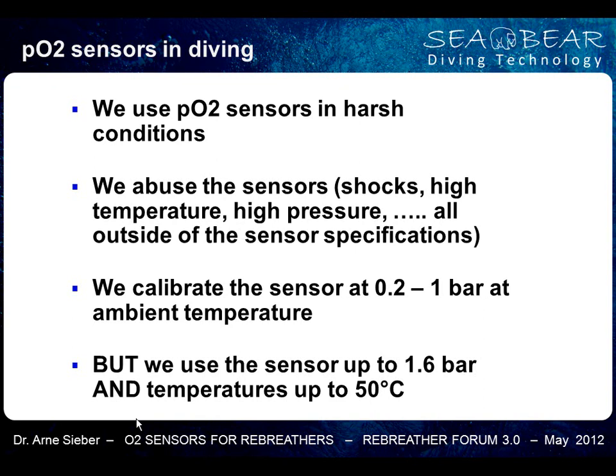The next thing is, we calibrate the sensor at 0.2 or maybe 1 bar PO2, and we're doing this at ambient pressure. But then when we are diving, we use the sensor up to 1.6 bar and temperatures up to 50 degrees, if it's at the exit of the scrubber. So this is not the same as what I have learned in the medical industry about how you should treat sensors. And this is when I said, this is not how it should be.